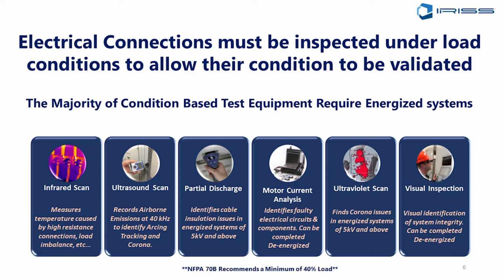Partial discharge detection, the other type, is where the defect is actually inside the insulating material. So it could be the cable insulation, it could be a standoff bushing or insulator, where when it was manufactured, there was a small void or defect inside the insulating material, basically a little air bubble, right? And on 5 kV and above equipment, what can happen is that arcs can actually occur inside of those voids in the insulating material. They will slowly eat away at the insulating material from the inside out. As they arc, they will degrade the material. Eventually, they can cause a failure to ground, all right, or a phase-to-phase failure.